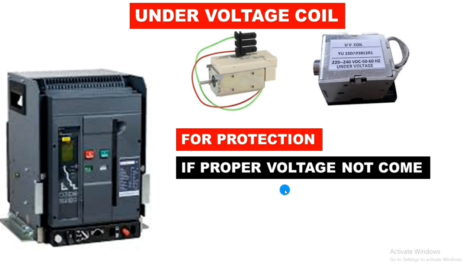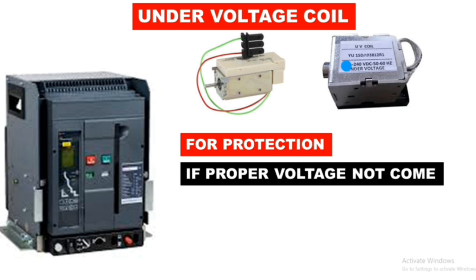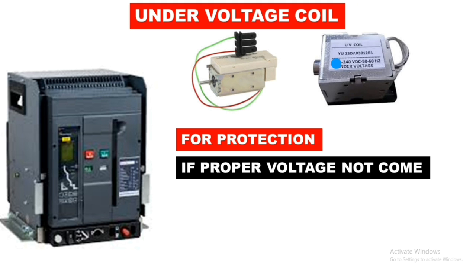The under voltage coil's main function is to trip the breaker if proper voltage is not coming. The under voltage coil should be connected at 440 volt so that if any phase is missing, this under voltage coil trips the air circuit breaker and the load will be safe. The main function of the UV coil is providing protection to our load.